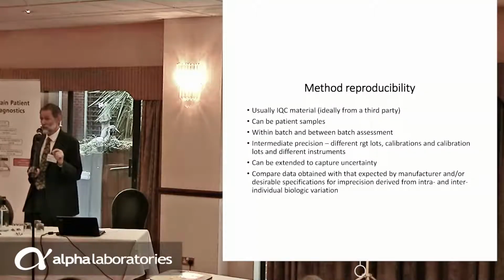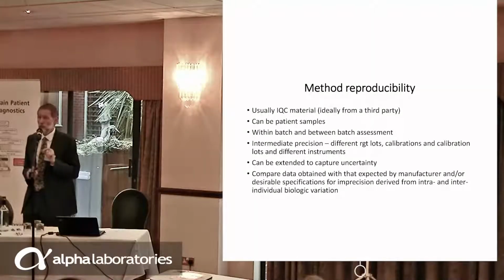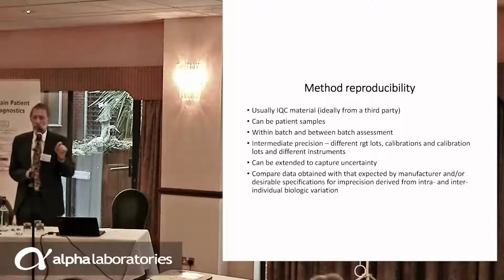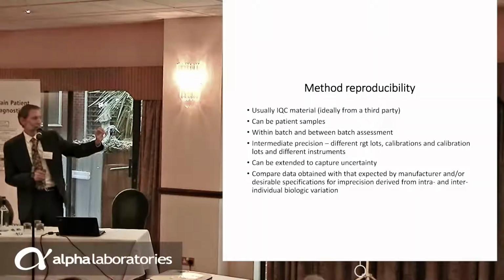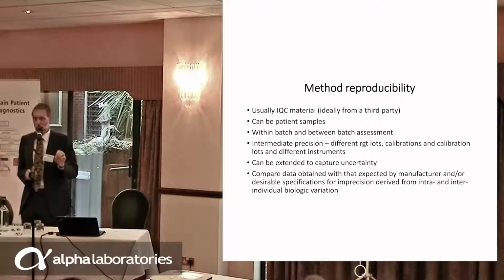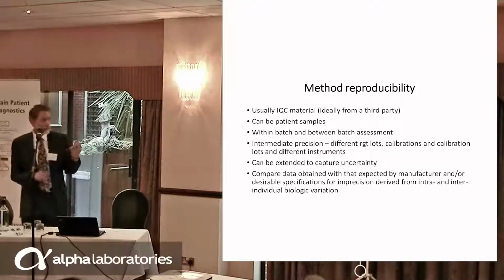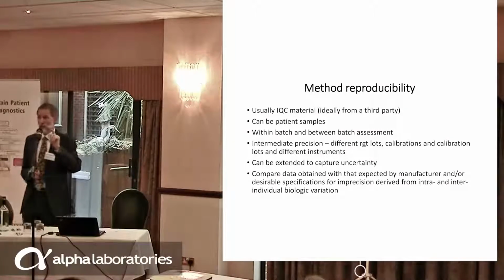And when you look at that method reproducibility data, you need to comment really, I think, on what the manufacturers have claimed. What I've observed, both in my own laboratory and in those that I've visited, is sometimes the precision claims of a manufacturer are over-egged. They'll tell you it's a fantastic precision, and when you've got your intermediate precision, it doesn't meet it.